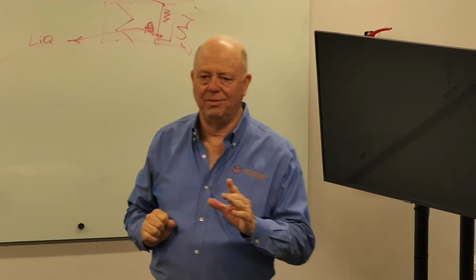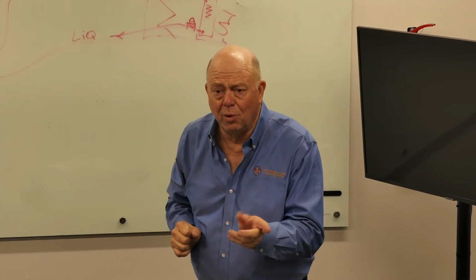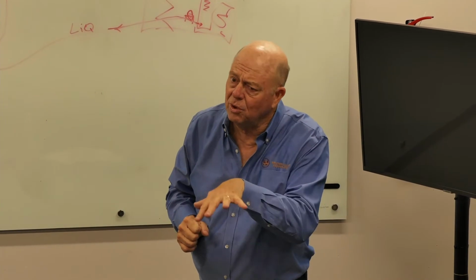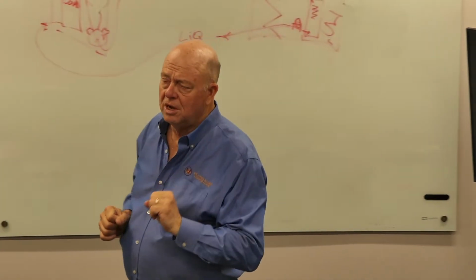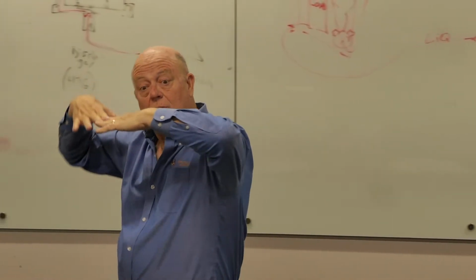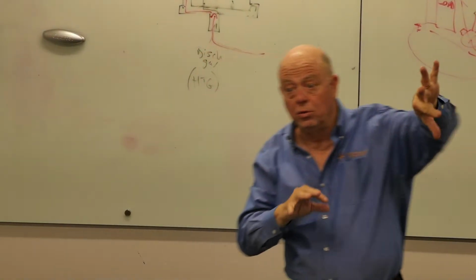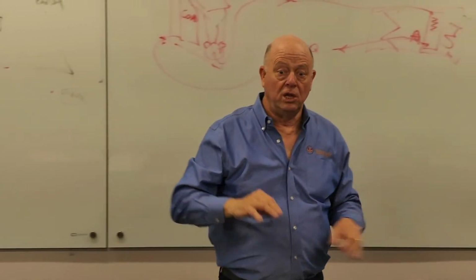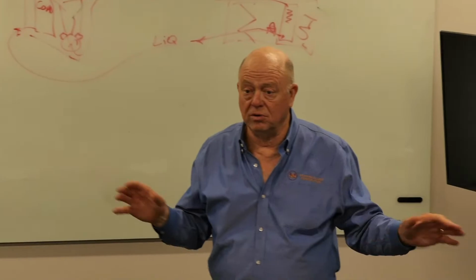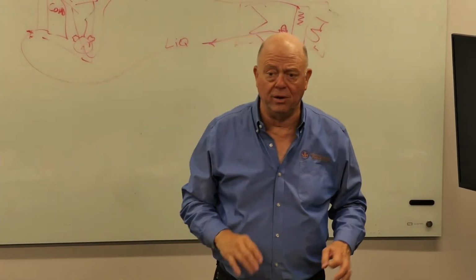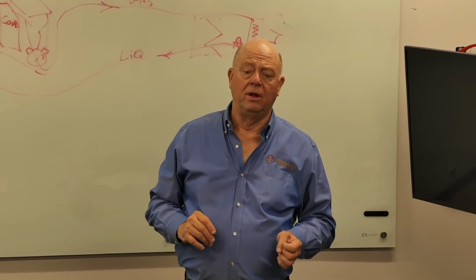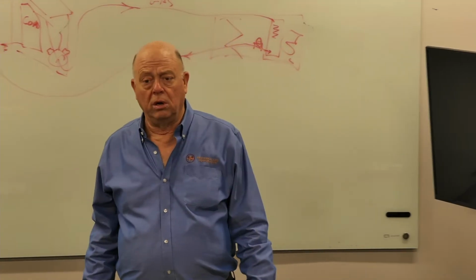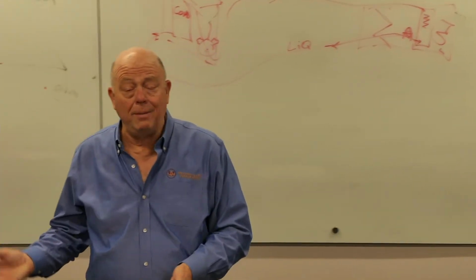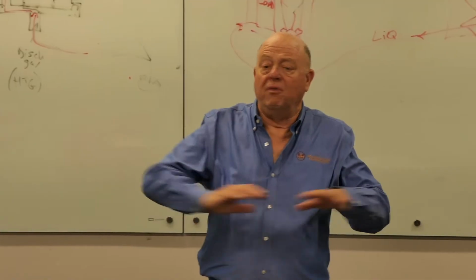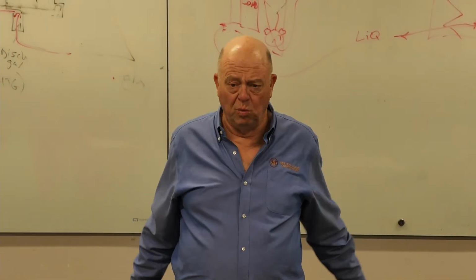The issue is getting the oil back to the compressor. If you don't get the oil back to the compressor, you've got a problem. So you had to have exactly the right slope on all the refrigerant lines. You had to have it sized just right and all that. And to make a long story short, it didn't work. Not that it wouldn't work in the laboratory if you did everything perfectly, but they never got installed that way and it just didn't work.